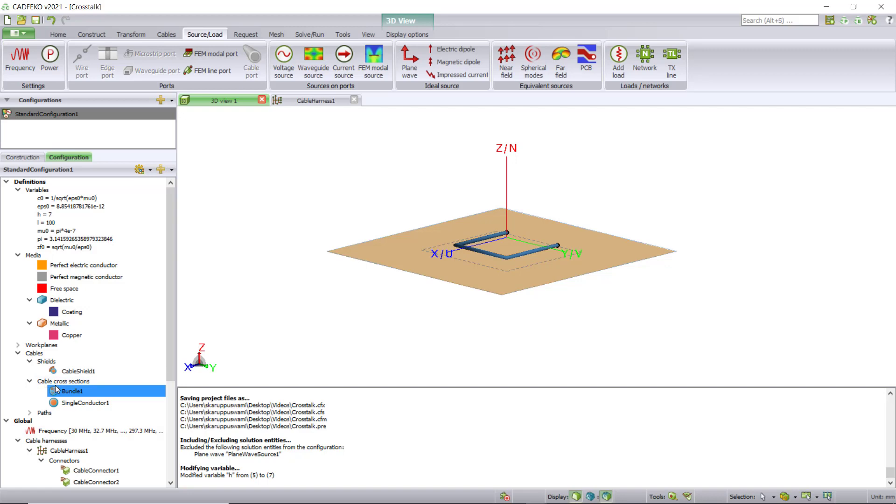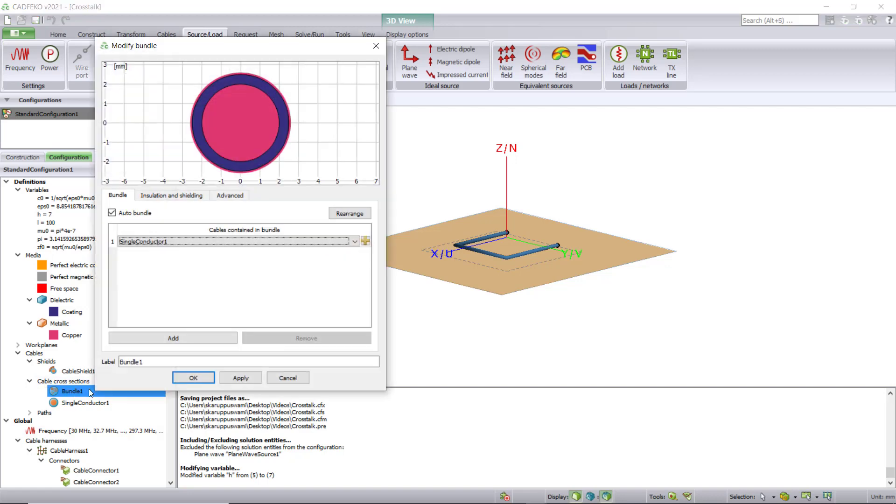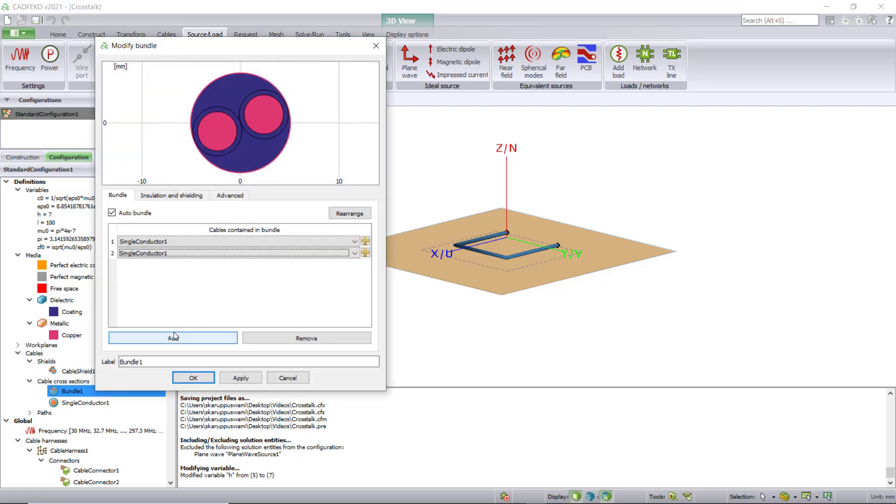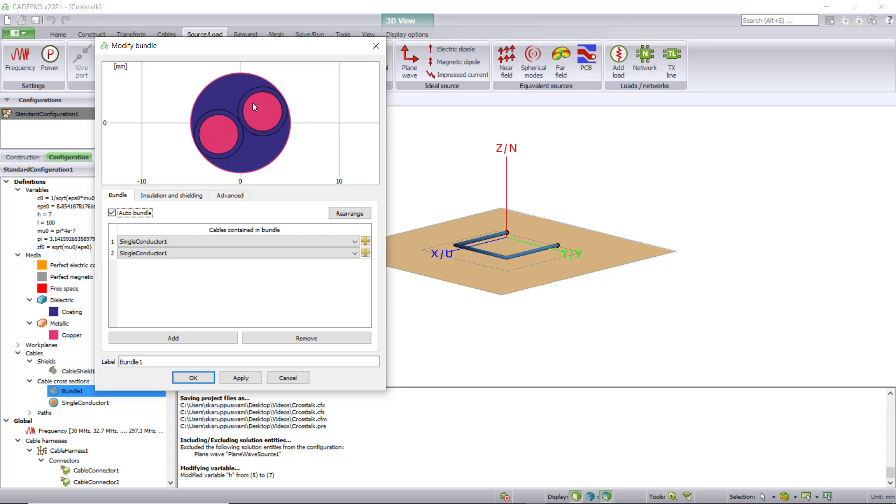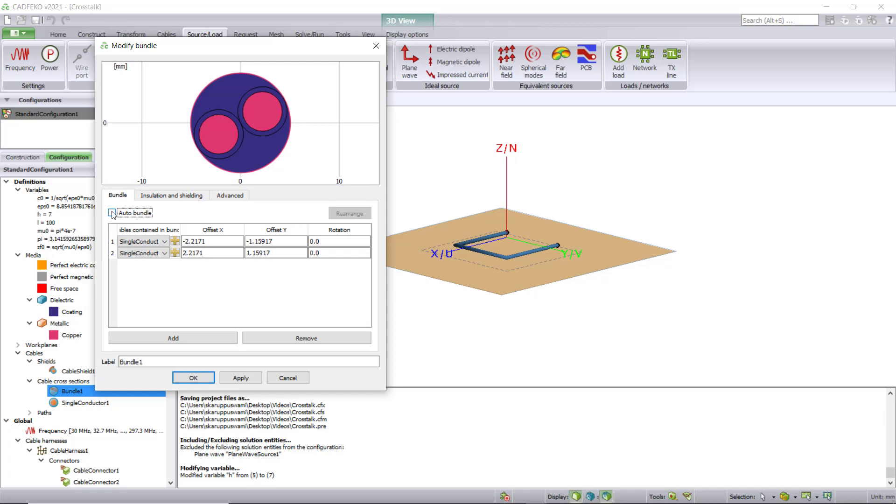Now click on Bundle 1 under cable cross section and add an additional single conductor. This will put two cables next to each other. If you leave auto bundle on, it will automatically bundle those two cables. But if you want to manually position them at a certain distance from each other, uncheck auto bundle and use the offsets. In this case, let's keep auto bundle on.